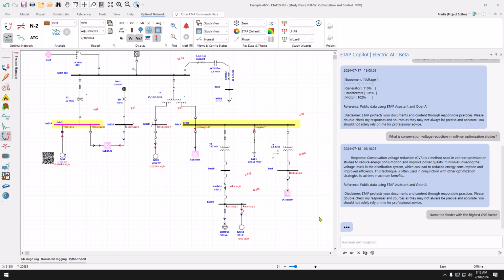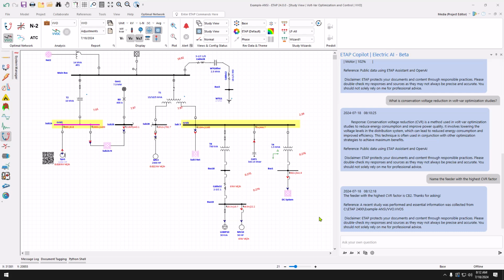It will tell me, based on the improvements ETAP has suggested from the voltage controlled devices, that the largest contribution is the feeder of CB2 coming through circuit breaker 2. So in this quick example, we can quickly see which feeder has the largest factor.